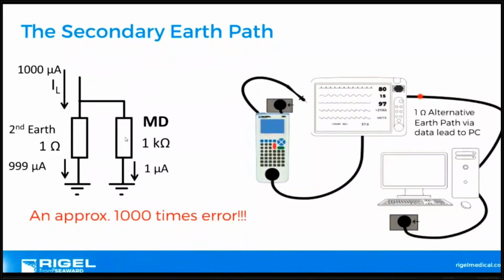Well, if you want to measure current effectively, if this was touch leakage or earth leakage, I want to show you how the fault current works. So this is my device, and internally I have this body model. I'm just going to draw it as a resistor. Any fault current will be in this circuit path, coming via the test lead.